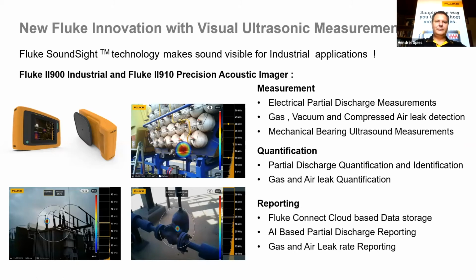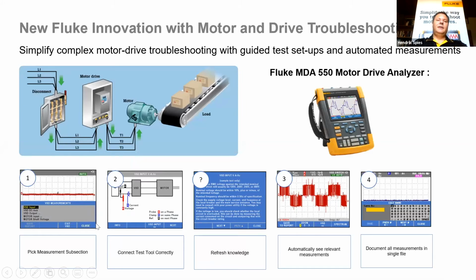Very quick screening tool. If you look at the second product, most of the industry has got motors and drives. So this is a typical installation where you've got a three-phase power supply coming into a drive or a variable speed drive. It's a system where we actually take the AC current and AC voltage. We do some modification in the drive itself, and now we can do variable speed to this motor, and we can control an application. So obviously this is a very complex system to test because the motor drive has got quite a lot of components inside, like the input, the actual DC bus, output, motor input. So there's quite a few parameters you need to be able to test.